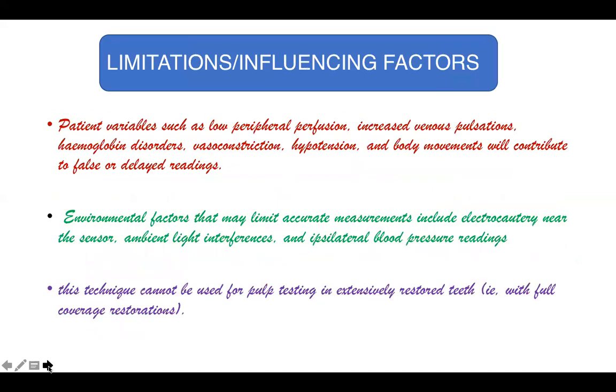Limitations and influencing factors of pulse oximeters include patient variables such as low peripheral perfusion, increased venous pulsations, hemoglobin disorders, vasoconstriction, hypotension, and body movements, which contribute to false or delayed readings. Environmental factors may also limit accurate measurements, including the presence of an electrocautery near the sensor, ambient light interference, and blood pressure changes.